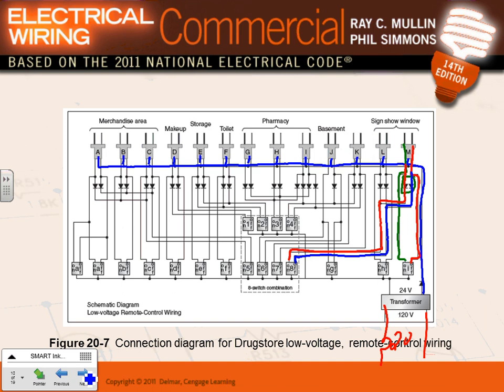And really, yes sir. You hit that master, you're going to turn both of those, both L and M, on, right? Yes, because the current is, I'm just showing only one. The current is going to continue here and turn this on, right? Right, and what else? In this case, you're going to turn these two together at the same time. Absolutely. When you have a diode like this, the current will go this way, but not the other way. So it allows the current to go one direction, not the other. That's what the diode is. So they use sets of diodes to control that 24 volt, right? They're connecting everything together, but they want the energy to go this way, not the other way. If I push this switch, I don't want the voltage to come and energize this one too. So that's why the current can't go down this way, but it can go up. Does it make sense, guys?